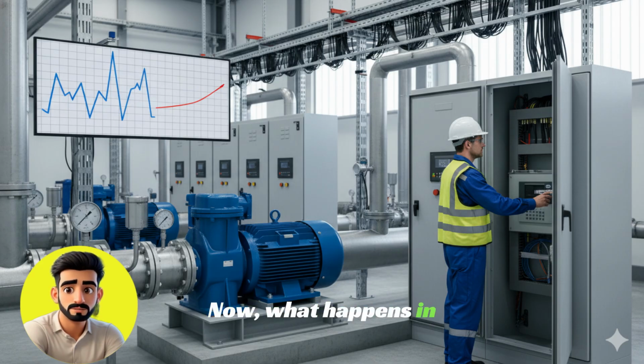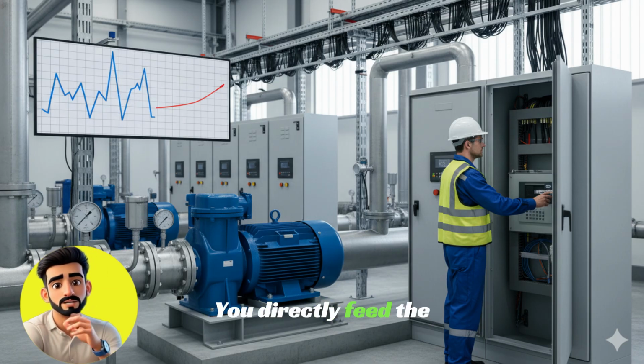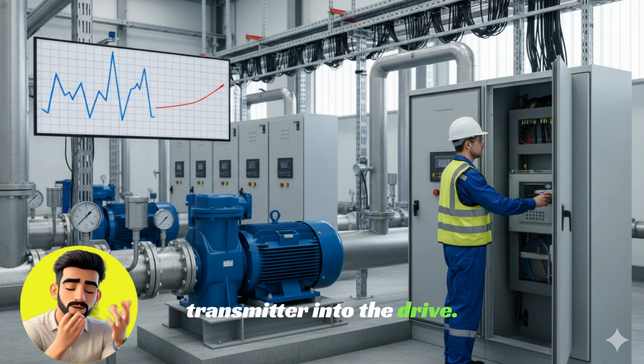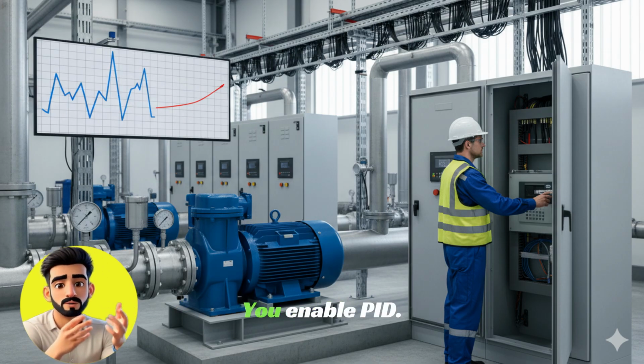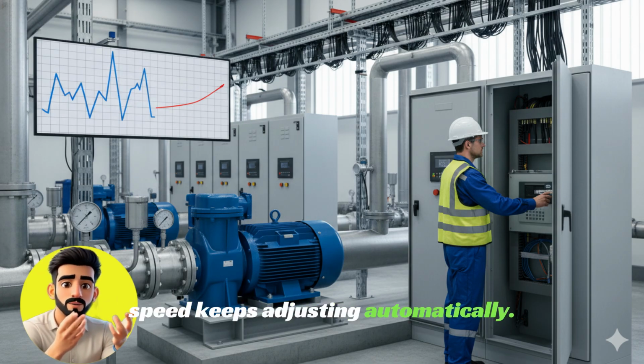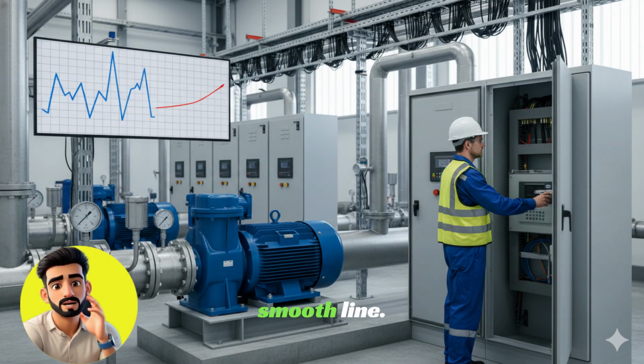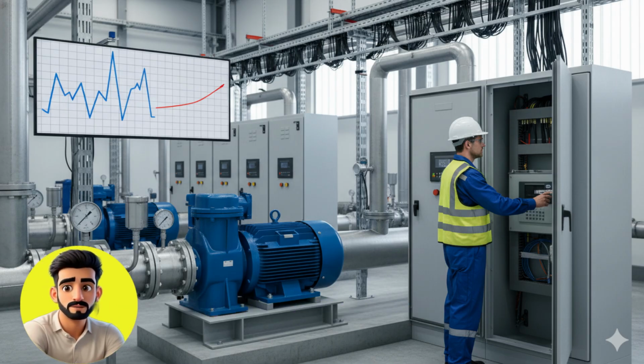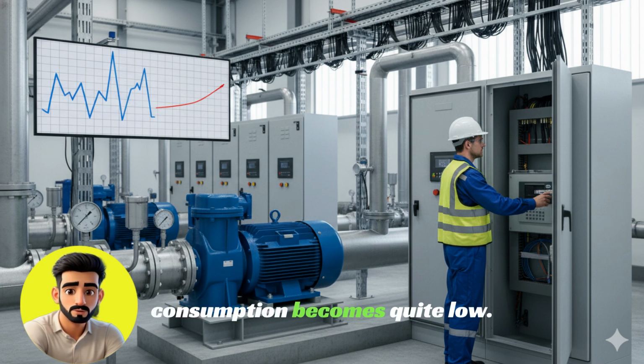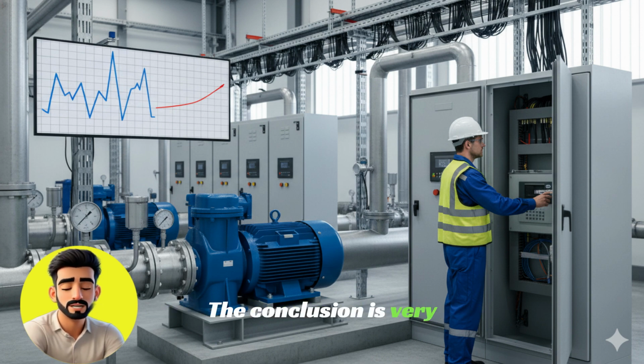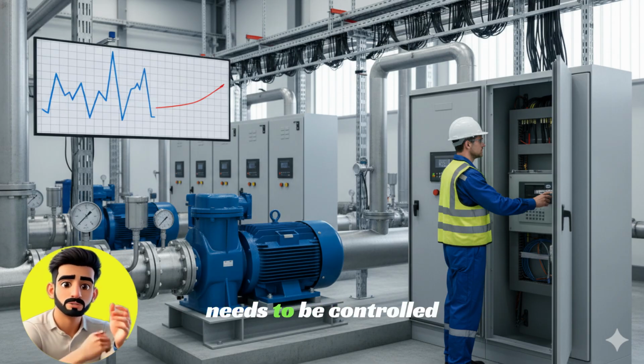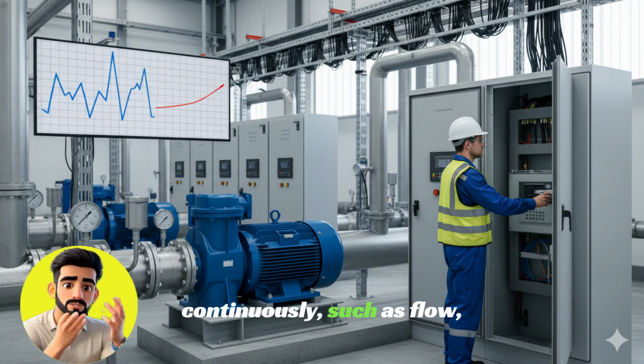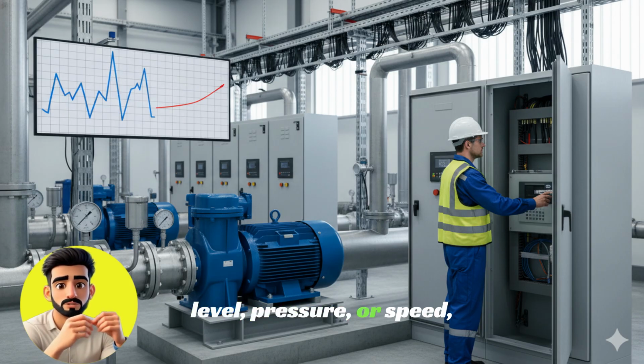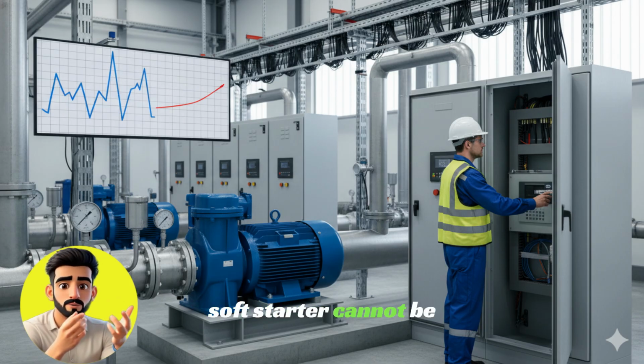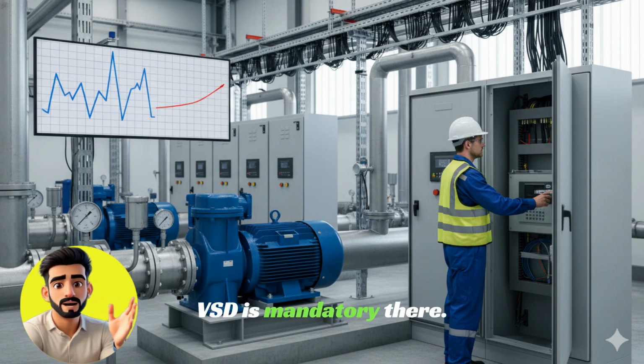Now, what happens in VSD? You directly feed the feedback from the pressure transmitter into the drive. You enter the set point. You enable PID. After that, the pump speed keeps adjusting automatically. Pressure behaves like a smooth line. The motor's life increases, and the system's energy consumption becomes quite low. The conclusion is very clear. Where the process variable needs to be controlled continuously, such as flow, level, pressure, or speed, a soft starter cannot be used. VSD is mandatory there.